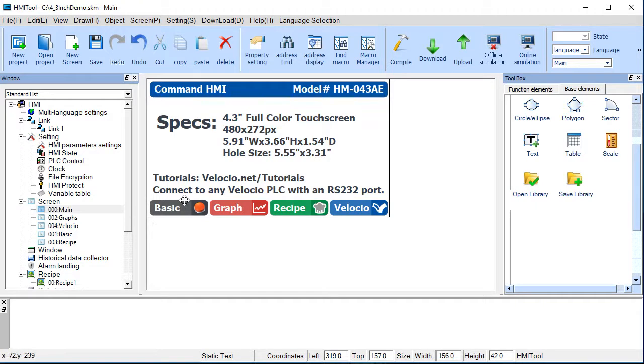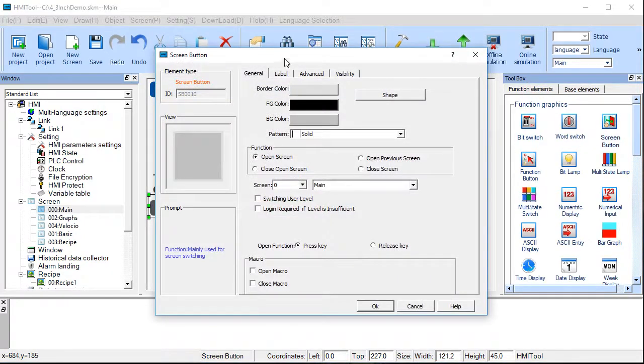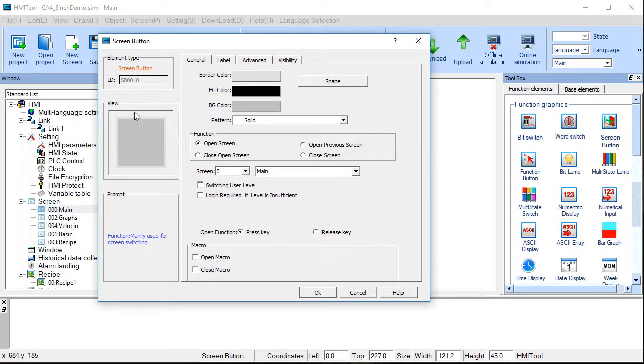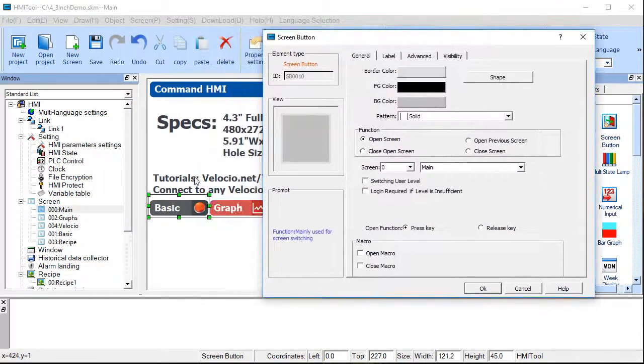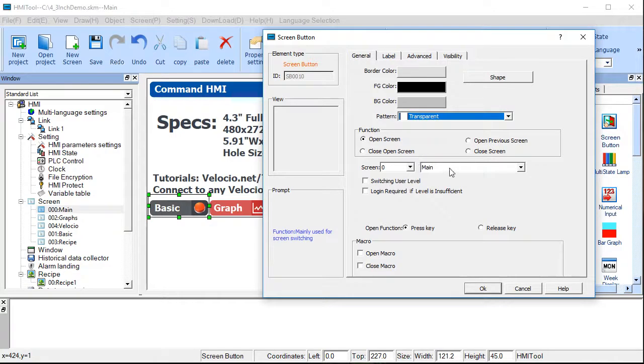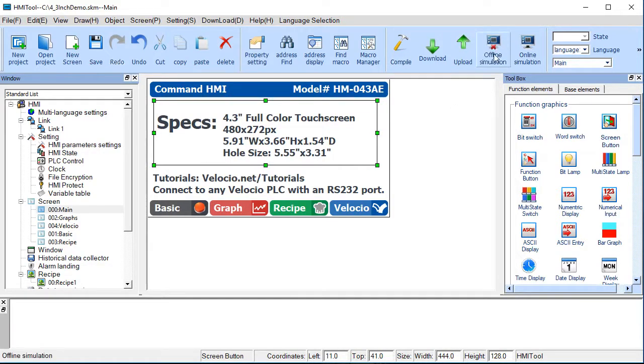The last thing we're doing on this page is the buttons. You'll find them here — they're screen buttons. Just like any other button you can change the color scheme and the shape. If you're using a background image and want a transparent functional button on the screen, you just change it to transparent and select the particular page you want to go to. Then you place it, and if you hit anywhere in that large area, it causes a jump to that page.